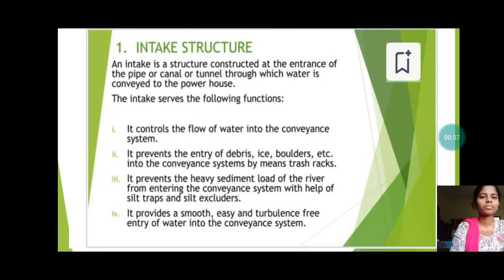Intake structure. An intake is a structure constructed at the entrance of the pipe or canal or tunnel through which water is conveyed to the powerhouse. The intake serves the following functions. It controls the flow of water into the conveyance system. It prevents the entry of debris, ice, boulders, etc. into the conveyance system by means of trash racks.